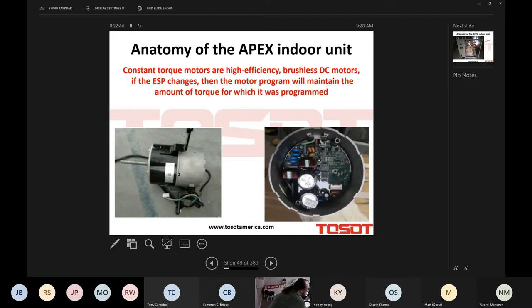I always find constant torque motors to be a bit of a double-edged sword. Yes, they try to overcome problems that may take place with external static pressure within a system, but they could also kind of band-aid or disguise a problem that really needs to be addressed. They're really there for the dirty filter situation.